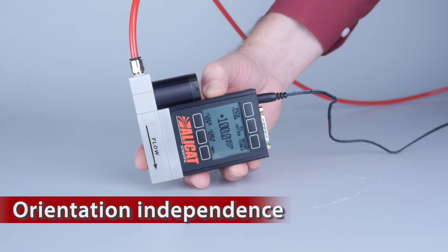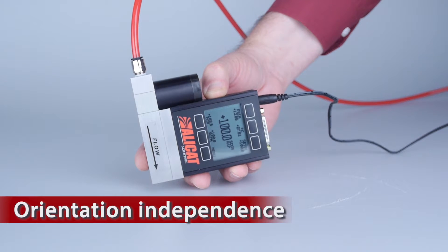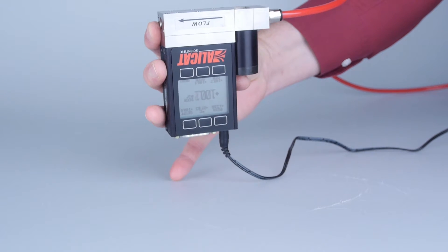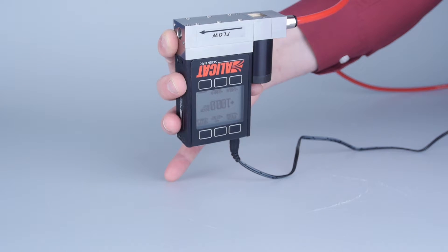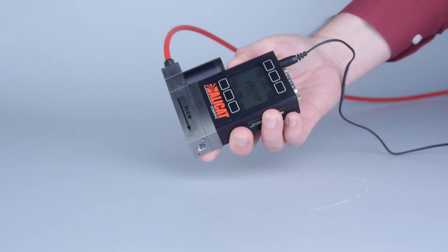Orientation independence: Alicat mass flow controllers can be mounted in any orientation, even upside down, without recalibration. And they don't require straight run lengths either, giving you more versatility in installation.